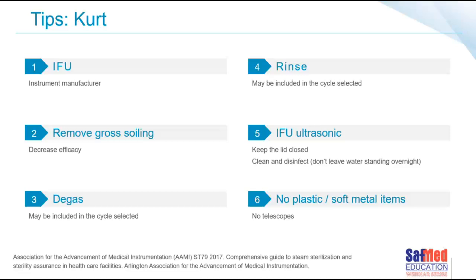Oh, okay, great. And rinsing? And rinsing. So rinsing, if it's a manual unit, we need to rinse before we put it through a washer or move forward with the instrument. It has to be rinsed off correctly. Make sure that there are no detergents on the instruments. If it's an automated unit and we have the correct cycle that we chose earlier, it will have a final rinse, which means it's rinsed and the water is drained out and it's ready to be put through an instrument washer or for its next phase.